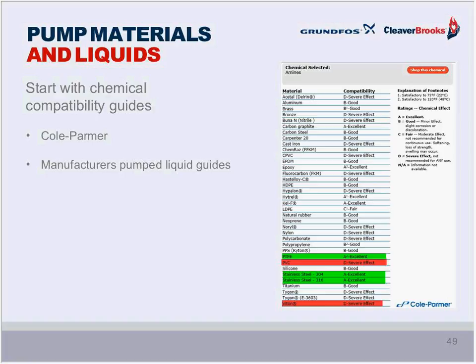A note on the liquids and choices of pump materials. This seems to be something that comes up often in discussions. Manufacturers publish charts that list a variety of liquids and materials that might be considered for use with each. In the zone here, we can see that amines, steel, and PTFE or Teflon are two of the best choices for material selection, while materials such as PVC and Viton show severe effects. Then there's Cole Parmer's online chemical compatibility database, my personal favorite.